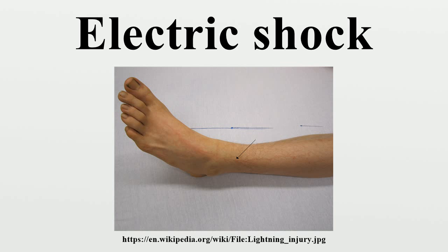OSHA found that up to 80% of its electrical injuries involve thermal burns due to arcing faults. The arc flash in an electrical fault produces the same type of light radiation from which electric welders protect themselves using face shields with dark glass, heavy leather gloves, and full coverage clothing. The heat produced may cause severe burns, especially on unprotected flesh. The arc blast produced by vaporizing metallic components can break bones and damage internal organs. The degree of hazard present at a particular location can be determined by a detailed analysis of the electrical system, and appropriate protection worn if the electrical work must be performed with the electricity on.